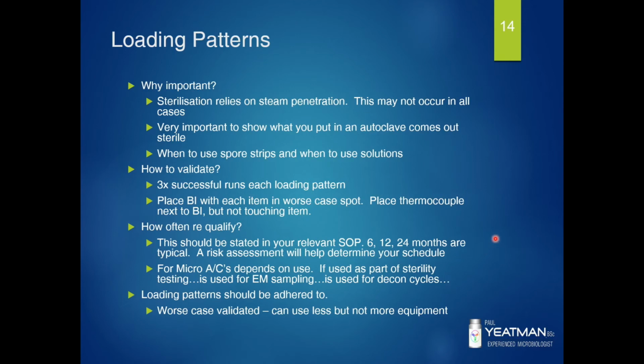How often you requalify depends on the use of the autoclave. Typically that'll be stated in the relevant SOP. It could be 6, 12, 24 months, all based on risk. So how much risk are you willing to wear? If you didn't validate every, say, 12 months, you did every 24 months, potentially you'd be looking at 24 months worth of investigation into potential risk to batch or impact on batch. So you can get away with it. The 6 months would be best because there's less investigative run around than say 24 months.